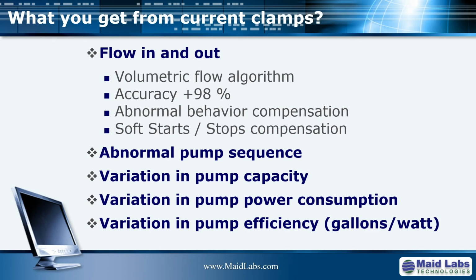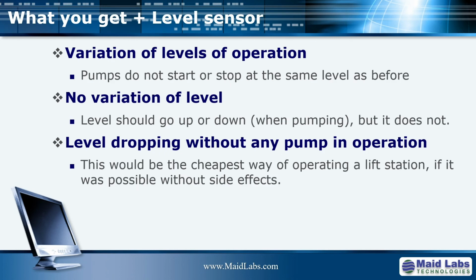There are two things. If you can connect a level sensor, then it will also check if the level of operation is always the same, if it varies, or if you have any kind of abnormal behavior like level dropping without any pump running. This is the cheapest way of operating a lift station, but usually it's because you have a siphon effect or the level sensor is defective. In both cases, it's bad.